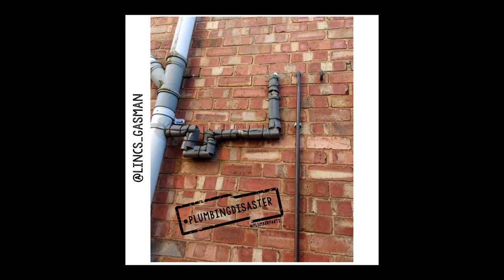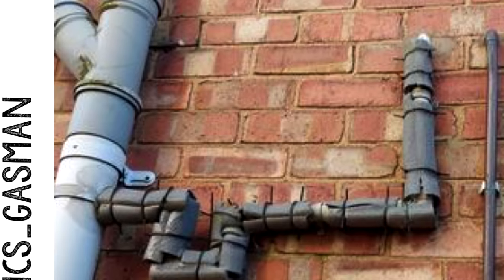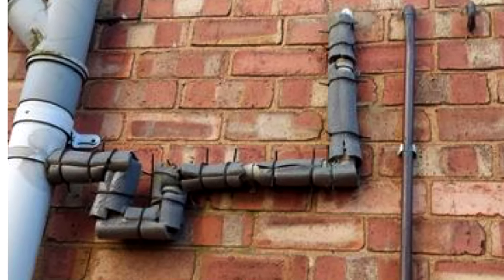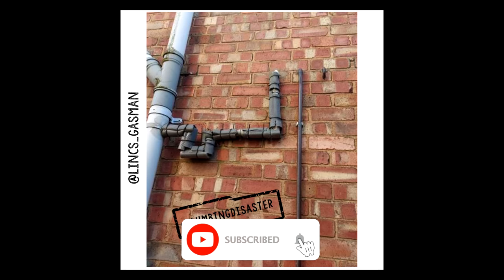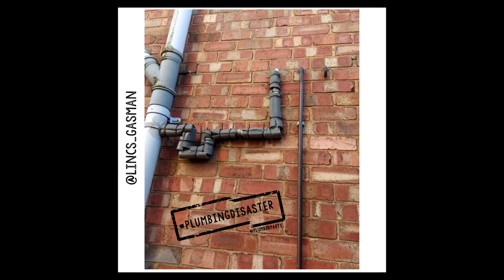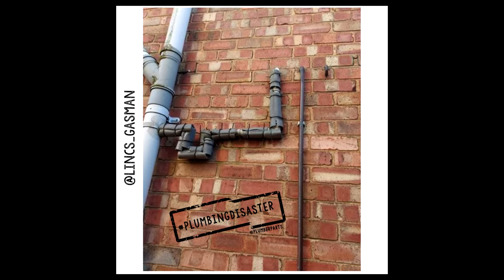Lincs Gasman found another condense pipe ready to freeze over in the winter. It's nice to see that they've used one metre's worth of insulation and about 50 tie wraps that they haven't even bothered to cut the tongues off. It's not going to do anything, it looks absolutely dreadful. And if it's minus 12 outside for any amount of time, it's going to beat that insulation — freeze that condense and make that boiler go wrong.